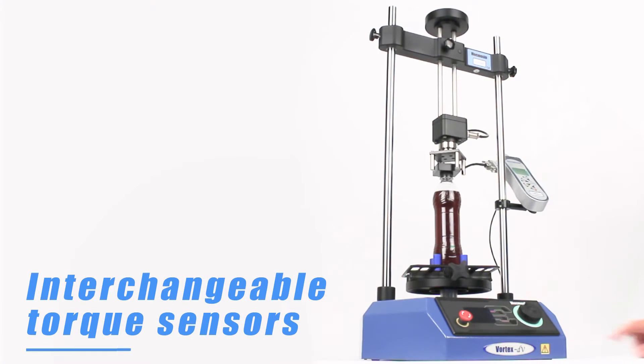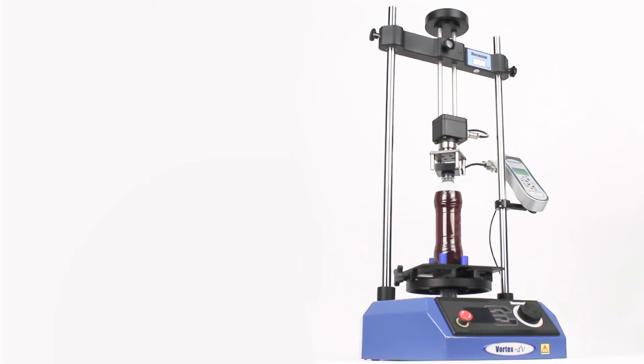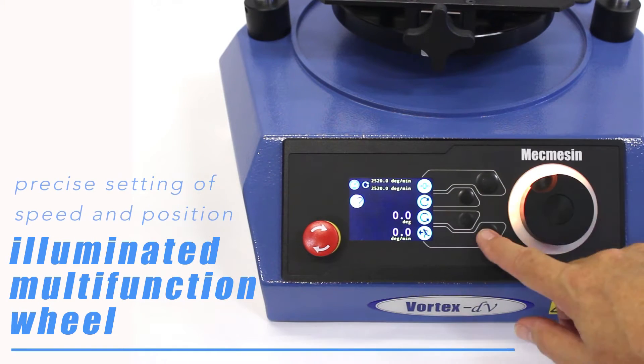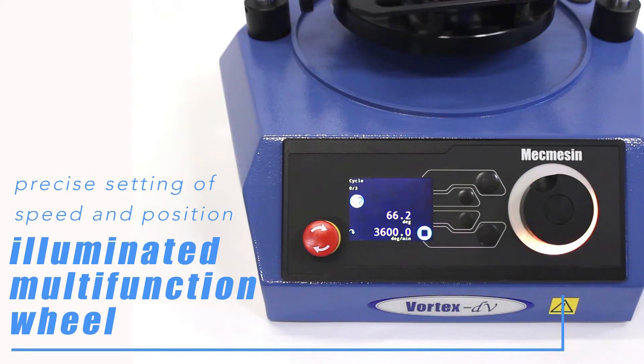Torque is measured by one of four interchangeable torque sensors which the AFTI display can show in either metric or imperial units as you require. The illuminated multifunction wheel is used for precise setting of speed and position. It's also used to accurately adjust the position of the sample before testing begins.